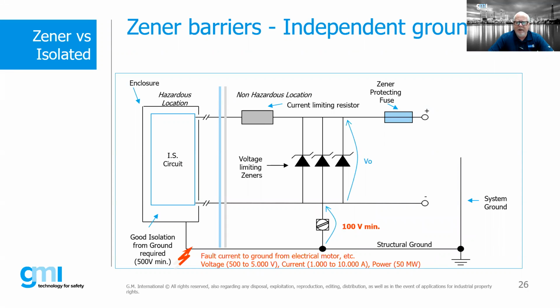Now, this is again an issue with the Zener barriers on the independent grounding, because if it is tied into our structural ground, then we could potentially have a fault condition coming back into the barrier itself or working its way into the field device via the structural ground. So it is really important that when we use Zener barrier products, we make sure that the safety ground is separate from our normal earth, our dirty earth versus clean earth.